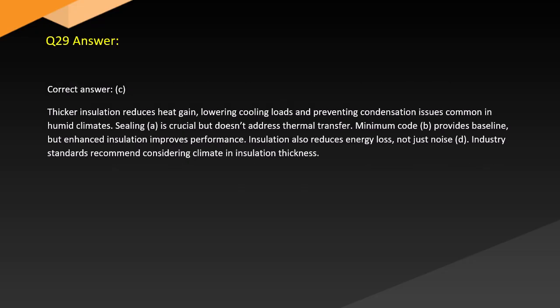Answer. Correct answer. C. Thicker insulation reduces heat gain, lowering cooling loads and preventing condensation issues common in humid climates. Sealing, A, is crucial but doesn't address thermal transfer. Minimum code, B, provides baseline, but enhanced insulation improves performance. Insulation also reduces energy loss, not just noise, D. Industry standards recommend considering climate in insulation thickness.